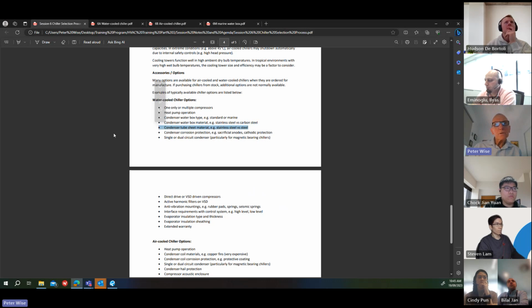Condenser tube sheet material. The tube sheets are what holds the tubes in place inside the heat exchanger. Depending on the size of the condenser, there might be a couple of tube sheets inside just to keep it rigid. And normally they will offer you steel for that. But again, it's an open system. They are subject to corrosion. So you can get stainless steel. You can get epoxy coated steel as well. So there's a few options there.